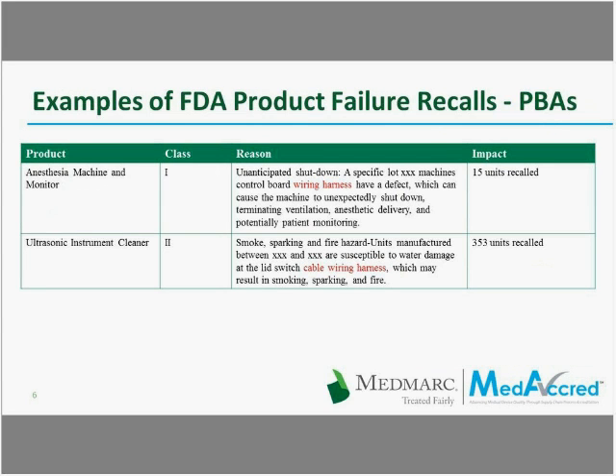Let's first take a look at 2 products that were recalled by the FDA. You can see the first one there is an anesthesia machine and monitor, and the reason for the recall was an unanticipated shutdown of a specific lot of machines. The control board wire harnessing had a defect, which can cause the machine to unexpectedly shut down, terminating ventilation, anesthetic delivery, and potentially patient monitoring. So you can see these pieces of equipment are so very, very important.